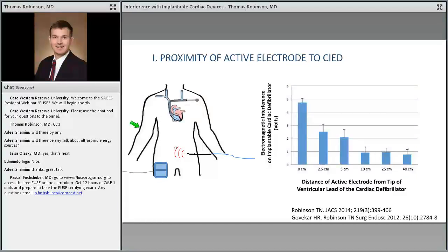What we did is we activated the active electrode. You can see 0 centimeters all the way to 40 centimeters. So we activated on the skin 0 centimeters below the sensing. A defibrillator or a pacemaker will typically sense right here at the tip of the lead. And so we activated it right over the top of it at 0 centimeters all the way down to 40 centimeters. And you can see there's a real dose response where you decrease the electromagnetic interference that's affecting the cardiac management device, which is up here, the further away you get. And you can see that it plateaued at around 10 centimeters away.